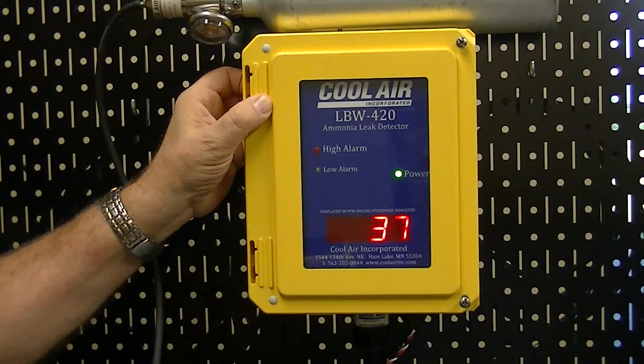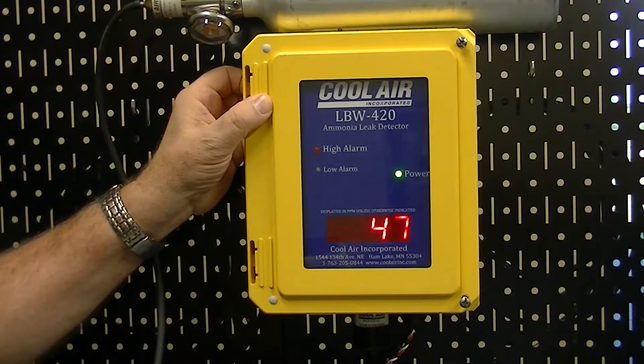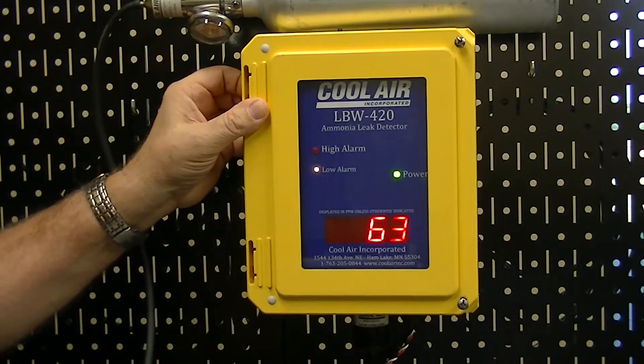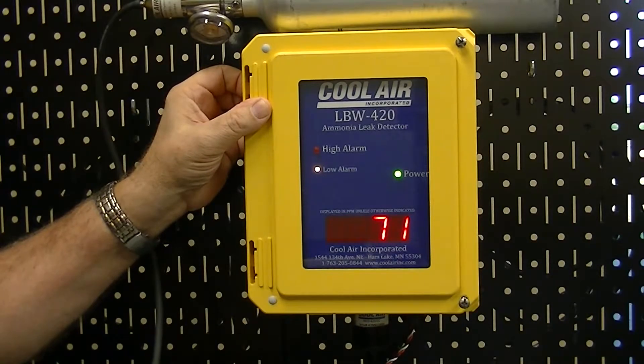You should see the display start to climb indicating the parts per million of ammonia. After two minutes we want to make sure that we're calibrated to the test gas bottle which is 100 parts per million.